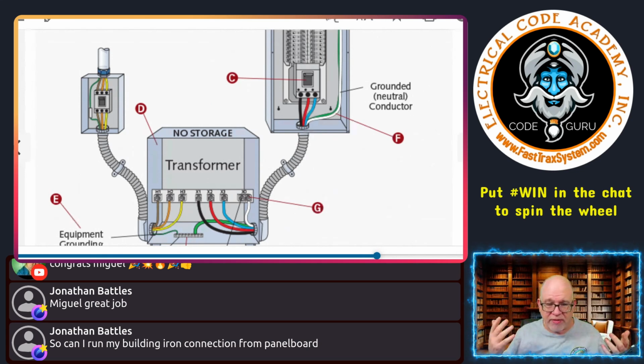concentric, eccentrics aren't going to affect anything. And your fittings are all going to be listed anyway for this type of wiring method, whether it's FMC or whatever it would be. So just normal lock nut, normal bonding is all that's necessary. Don't have to worry about it because chances are, again, it's not over 250 volts to ground. And these obviously are not service conductors. So again, it's a standard, cut the hole and done. Now, even if you had concentric or eccentric, there's a high probability that these are not over 250 volts to ground. So normal lock nuts would be fine. Everything else would be fine, and they'd be considered bonded because you're using all listed components.